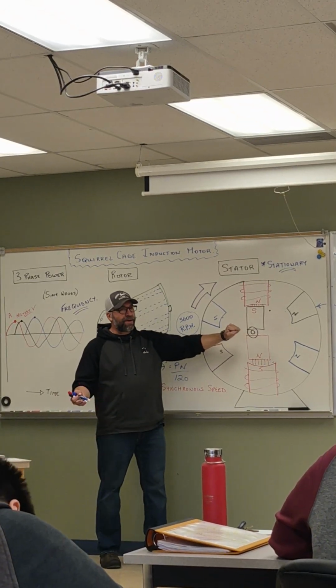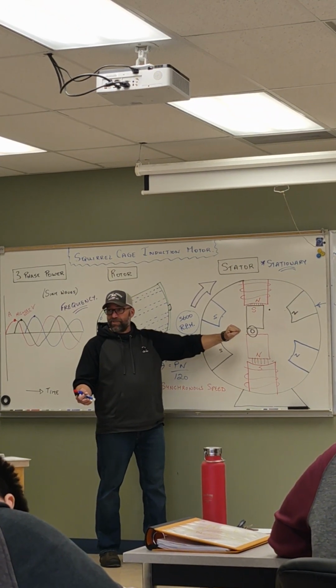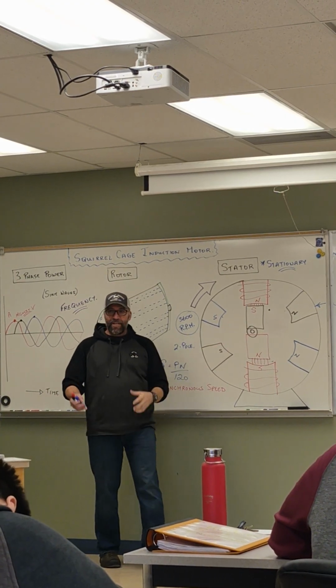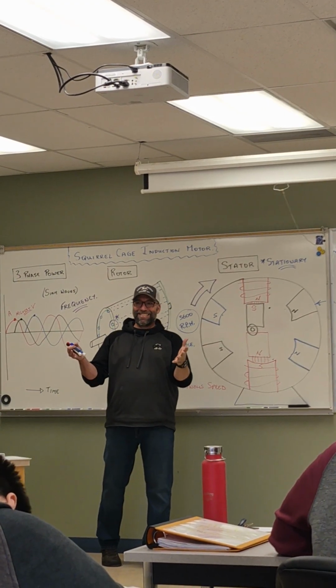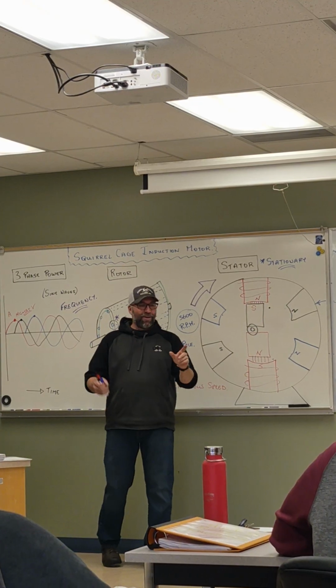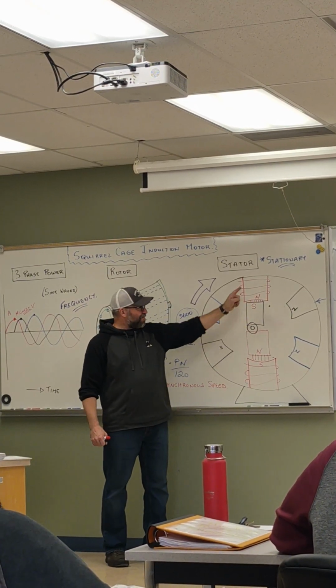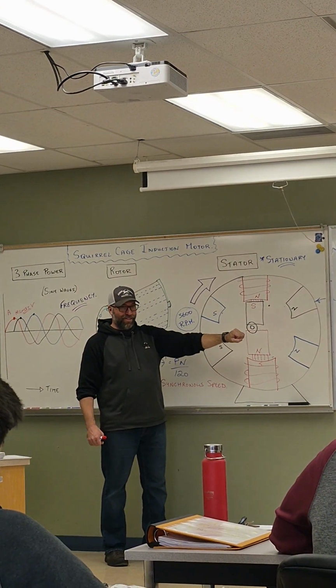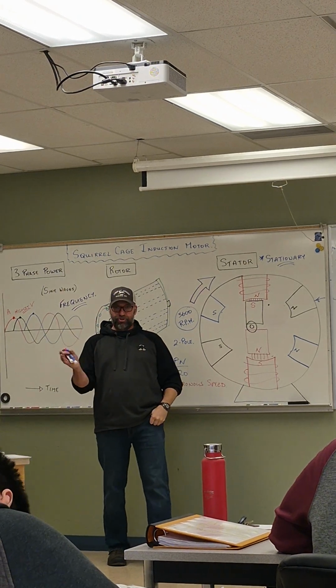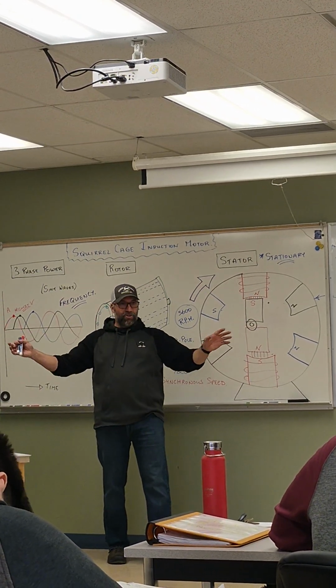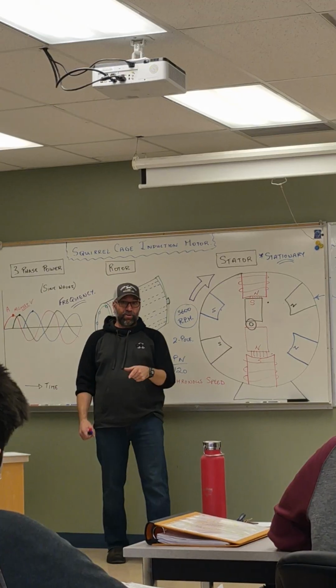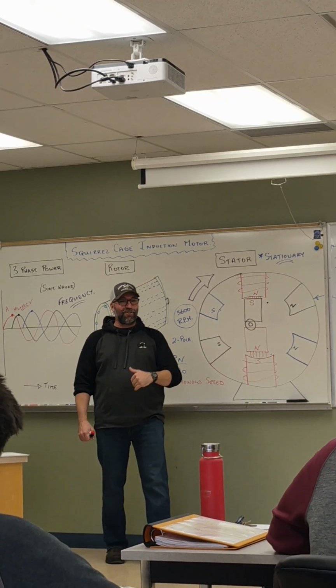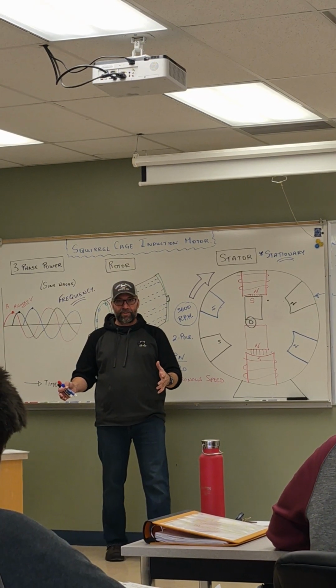we have what's called tearing out of synchronization. And you can absolutely hear it when it happens. You got a motor that's running, and as you load it up, when you break this magnetic field from this magnetic field because you put too much load on it, suddenly it goes, and your gauges are all over the place. What the hell is going on? That's overloaded. It's like, no. Take the load off, you've overloaded it, you've broken it out of synchronization.